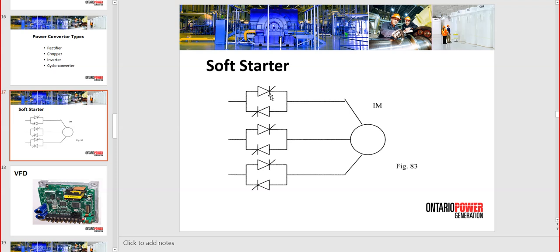So by chopping the 60 hertz sine waves, like half sine waves or stuff like that, you will inject a lot of harmonics in the motor. So there is no motor that can keep up with that. A soft starter is always with a bypass contactor on each phase. Once the motor reaches full speed, the contactor closes, and the soft starter, through a logic, can move to another motor to start if desired. It's typical for water treatment plants where you have to start up to 40 motors. You have the same soft starter moved around and you start whichever number of pumps you need.